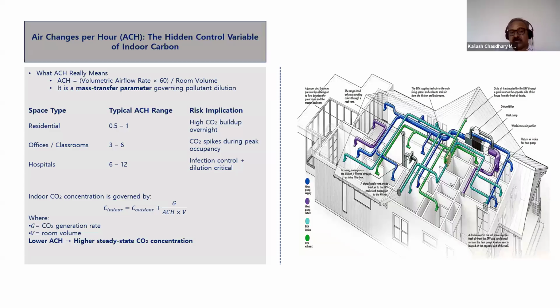So what is the trade-off? A lower ACH, air change per hour, reduces outdoor particulate entry. But the indoor CO2 accumulates, cognitive performance declines, and occupant comfort suffers. If you increase the air change per hour, the high PM 2.5 enters. The filter will be clogged quickly, and the pressure drop rises. Fan energy will increase. The filtration is really weak because it's already clogged. So we are forced to inhale hazardous particles.